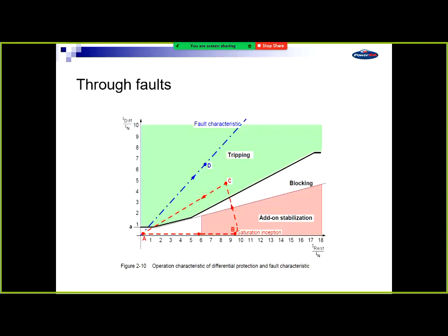Now that's what they say, that's not what they guarantee, that's what they say and how their things operate. There can be a safety margin in there. My preference is to set your CT so it won't saturate. Then you don't have a problem with CT saturation. But you need good quality CTs to do that. So that's why we order the PX class and order good ones. We actually allow our CTs to saturate at maximum fault level, so a fault level of about 40 kA and an X/R of 20. We only have a few sites like that, close to the synchronous generators. They have a high X/R and a high fault level.